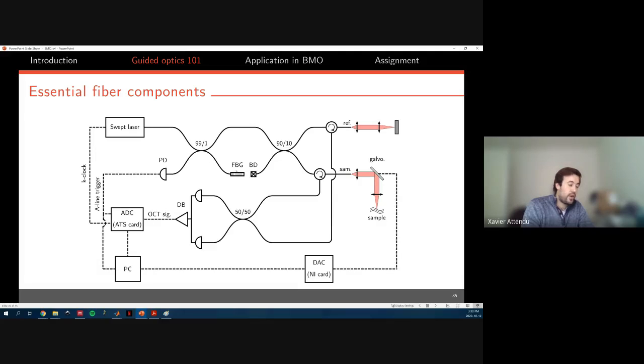Now here we have a fiber Bragg grating, which we made exactly such that only light at a specific wavelength is going to be reflected backwards, right? So for the swept source OCT, let's say it sweeps from 1200 to 1300 nanometers, and this fiber Bragg grating only reflects light at 1250. Every time it sweeps, there's going to be a pulse of 1250 light that goes back to this detector. And this can act essentially as a sweep trigger. So every time it does a sweep, this detector here will receive a pulse, and that's one way we can know that it's sweeping. Okay?